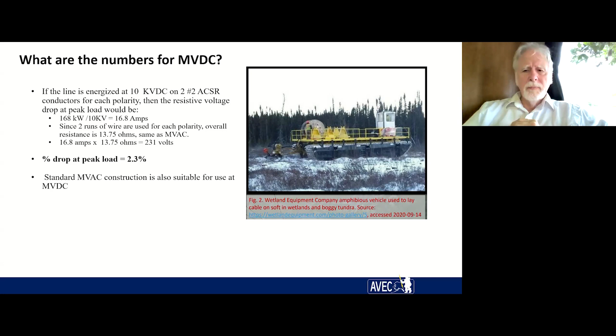So again, trying to keep the cost down to start. To use cables, the whole point actually of using MVDC is to be able to use cables. They cannot be used for any appreciable distance at light loads using AC for technical reasons. But you can go almost unlimited lengths using MVDC with cables. And cabling is just about the only way I can see that we can do interties between villages with a lower capital cost of installation and a much lower cost of maintenance, being underground or under the water.